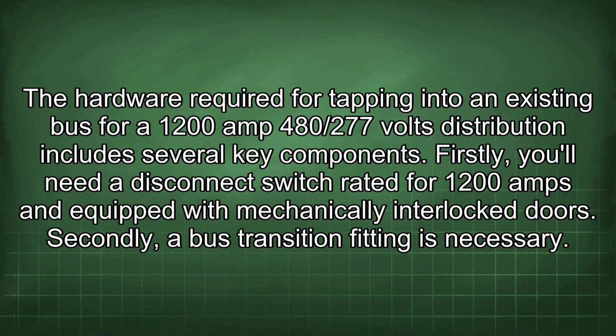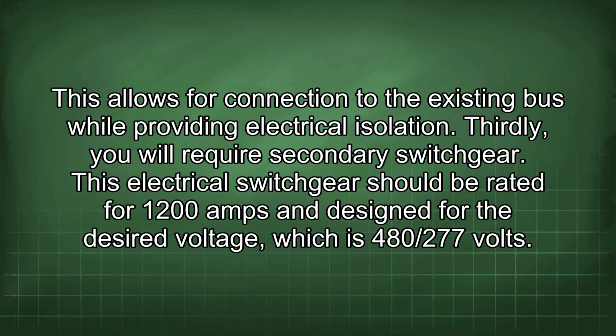The hardware required for tapping into an existing bus for a 1200 amp 480/277 volts distribution includes several key components. Firstly, you'll need a disconnect switch rated for 1200 amps and equipped with mechanically interlocked doors. Secondly, a bus transition fitting is necessary. This allows for connection to the existing bus while providing electrical isolation.